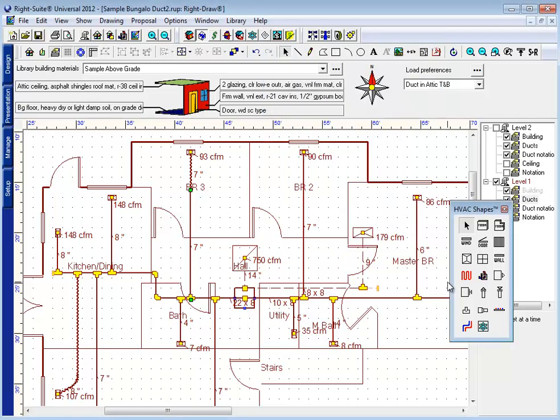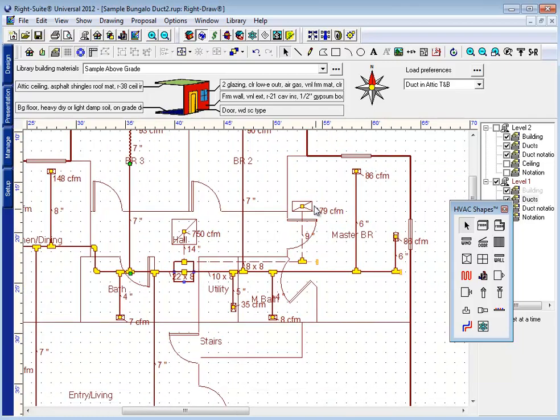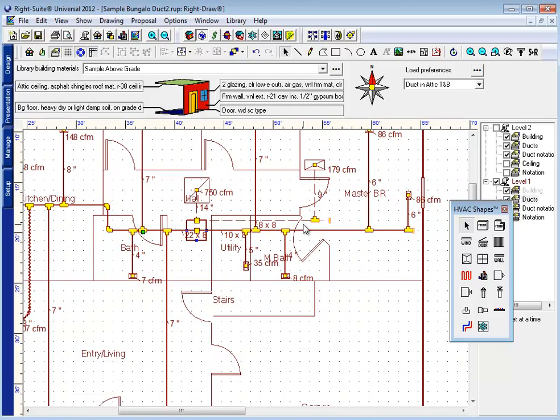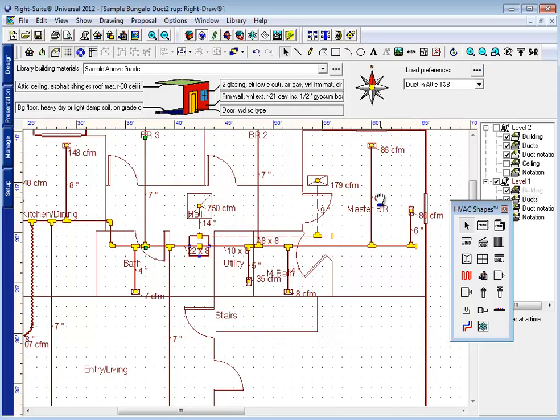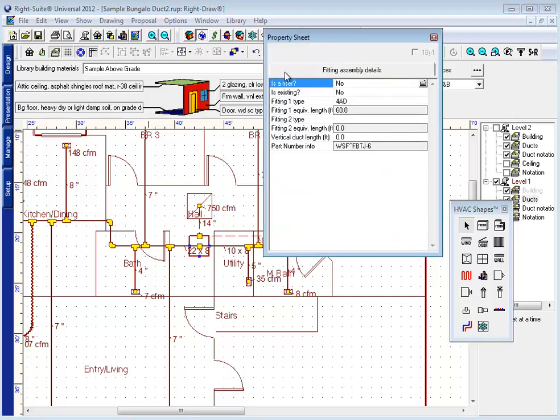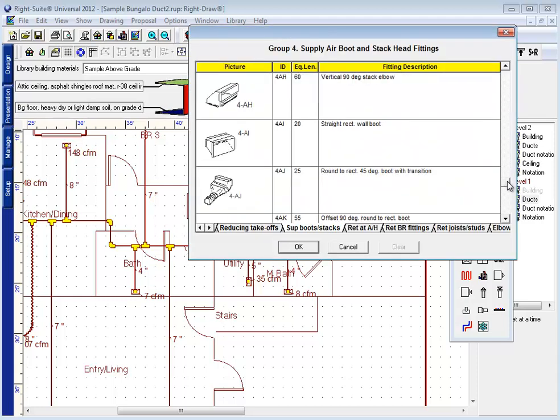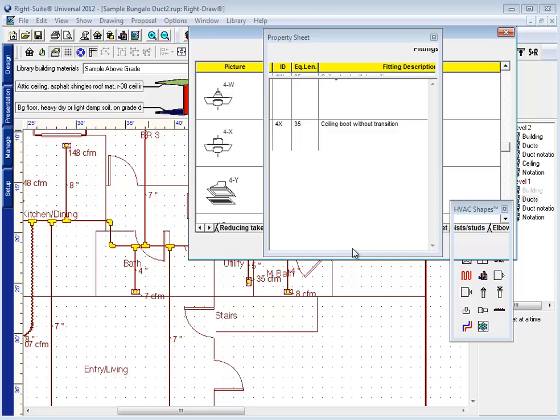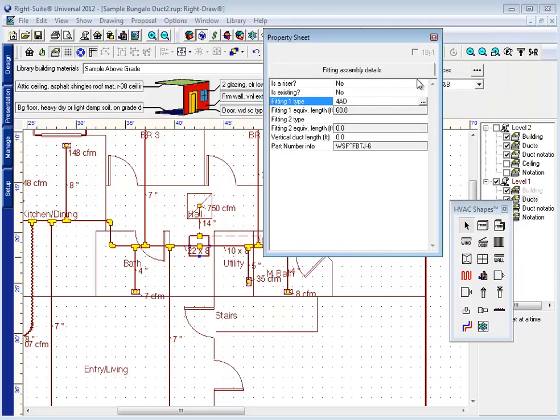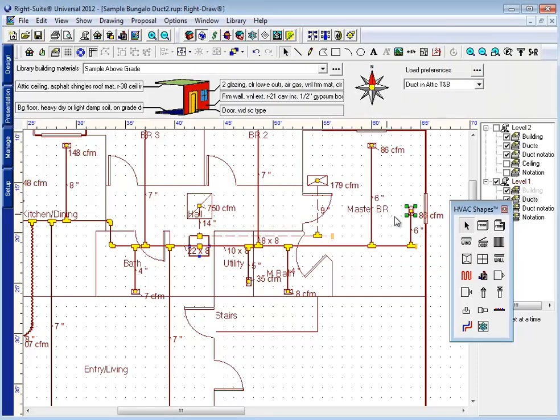Another common thing you might do while editing a duct system is adjusting individual fittings. If the majority of your boots are straight boots, but a few of them are parallel or torpedo boots, you might want to make adjustments to those individual boots. Simply right-click on a boot, or any fitting for that matter, and you can manually make adjustments to what kind of fitting you're using there. It should be noted that any fitting that you manually adjust or override will not change if you should change your duct preferences later on.